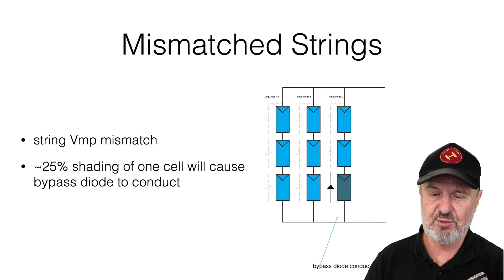Now, there are ways to overcome this. Good design, multiple inputs to an inverter which have separate maximum power point trackers, module level power electronics such as microinverters or so-called optimizers, which really overcome this loss due to a module being bypassed. But if the site doesn't have shading or doesn't have significant continuous shading issues like a panel behind a chimney, then it's not really a big deal. So this is the last of my slide deck, just showing all of the panels now being shaded, and so they've actually taken themselves out of circuit, and therefore we've lost 1/3 of our production.